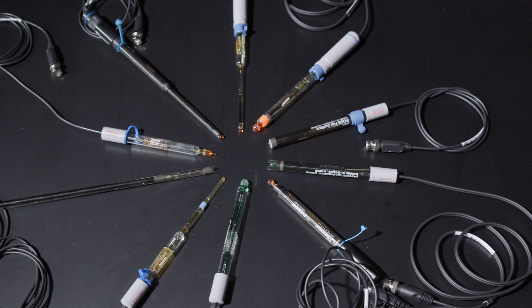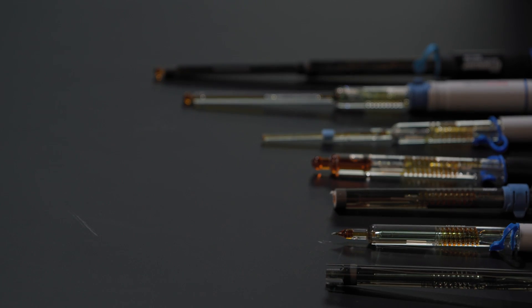Samples with extreme pH values require specific electrodes to obtain accurate readings. This means using electrodes that are sensitive across the entire pH range from 0 to 14 pH units. Historically, not all pH glass has been able to read across the full pH range. All Thermo Scientific Orion standard and advanced electrodes have this capability.